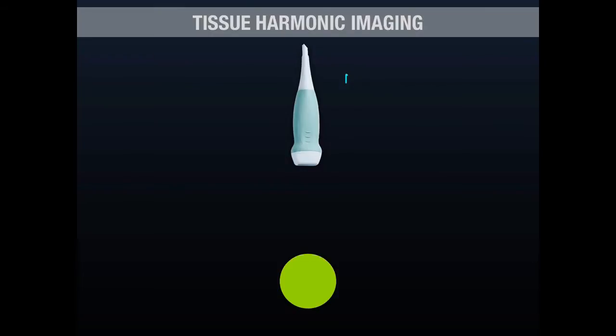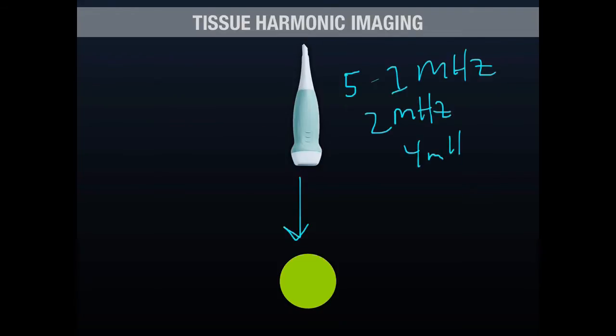So, in this case, you're pulsing a signal at 2 megahertz frequency into tissue. And harmonic frequencies arise at 4 megahertz, at 8 megahertz, and so on, at multiples of the original fundamental frequency. And the way to think about this is if you strike a tuning fork and listen, it rings at that frequency, but you hear the higher harmonic frequencies on top of that.